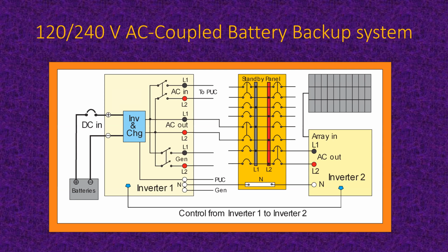And what can the inverter do with it? It can't send it out to the utility anymore. So the only option it has is to charge the batteries. Well, you can only charge those batteries so far, and then they start getting unhappy. What they do is their voltage goes up, and the inverter senses that the battery voltage is as high as it can go without damaging the batteries. So the inverter then has to talk to the other inverter and say, you've got to slow down a little bit here, because we don't have anything to do with that extra electricity you're making. So you see that control wire at the bottom. Now that could very well be a wireless control, but it's nice to show it as a wire just to show that they have to talk to each other.